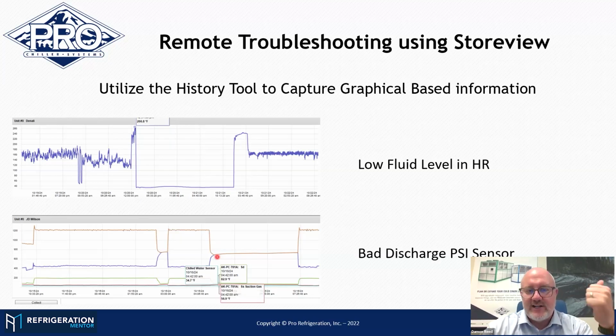I mean, we're looking at discharge temp, we're looking at the chilled water sensor, we're looking at suction gas temp. So then that's where we make the call: okay, I've got to get out on site. And when I say I, I don't mean I personally. I mean the mechanic, the technician that services the equipment, goes out on site to see if these pressures are right. Is this making sense? And in this case, we were actually getting up to 1500, 1600 psi, but there was a faulty discharge pressure sensor.